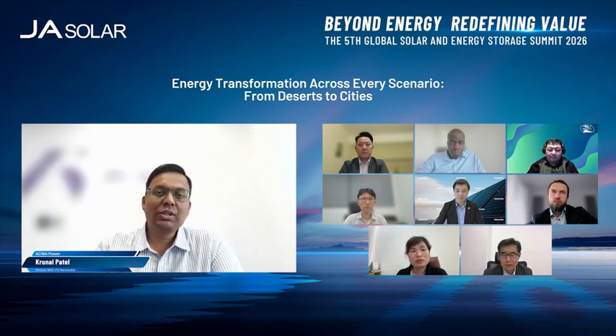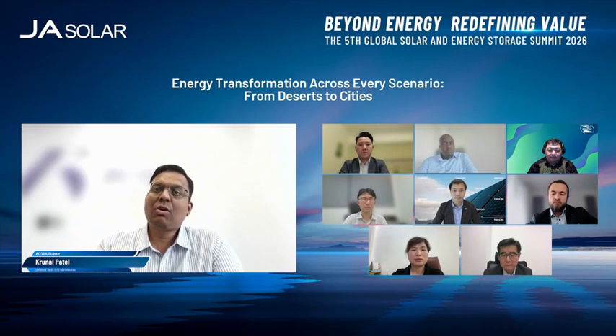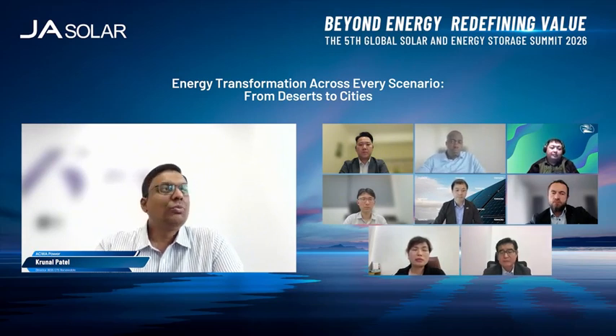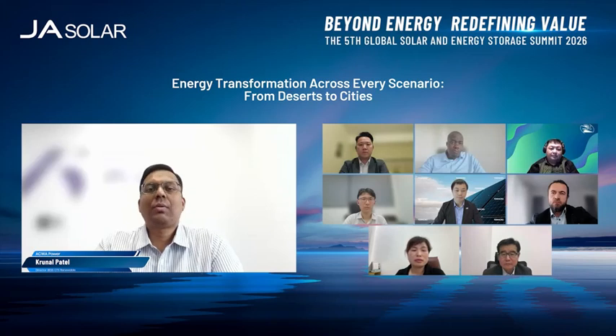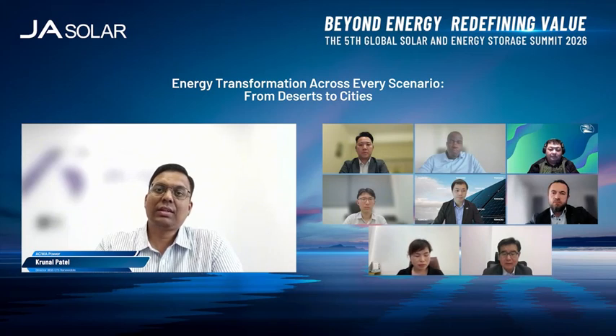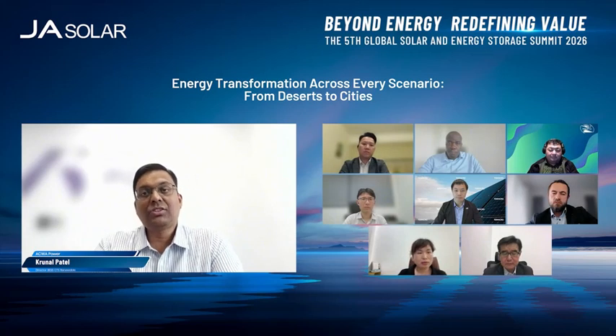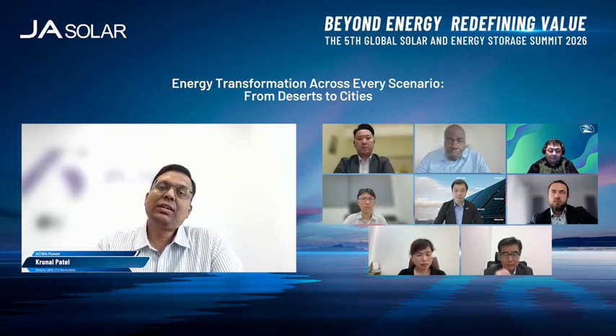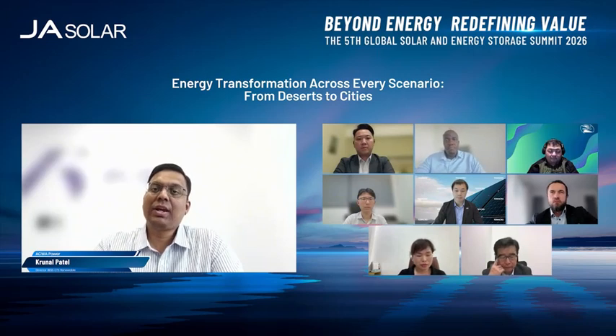The second harsh environment condition affecting various projects is that meeting performance guarantees becomes more challenging nowadays. When you move from lab condition requirements to operating environments, factors like auxiliary consumption, partial loading, and thermal derating can significantly impact round trip efficiencies as well as the availability of the plant. This makes the definition of measurement points, whether DC, AC, or MV level, commercially critical in various contracts.